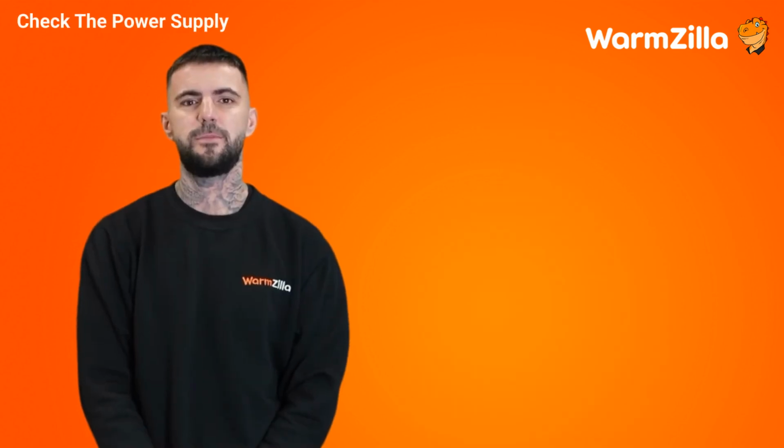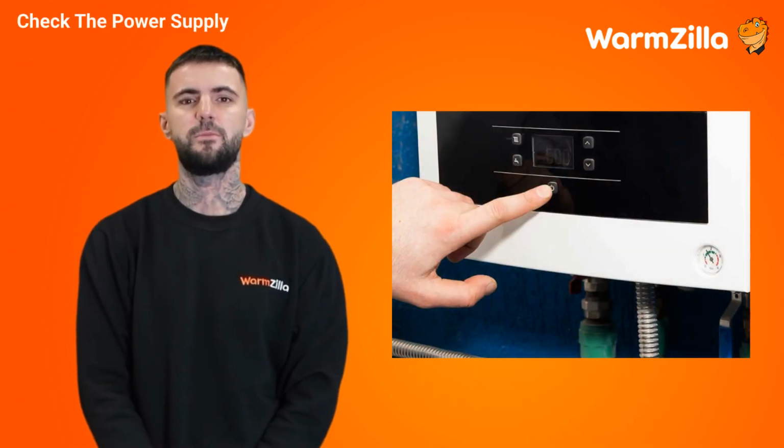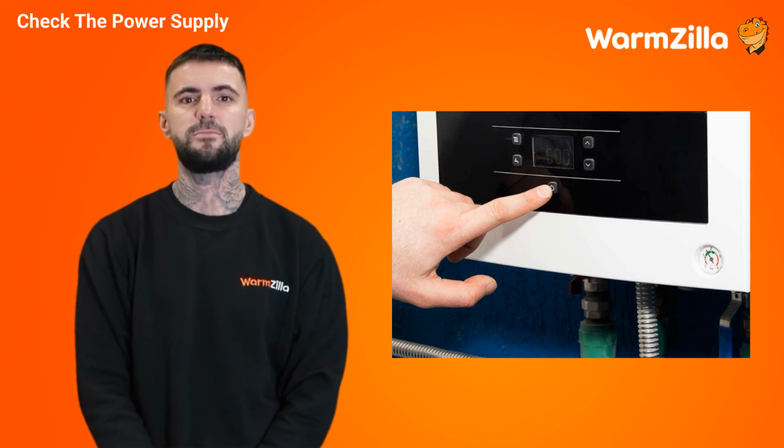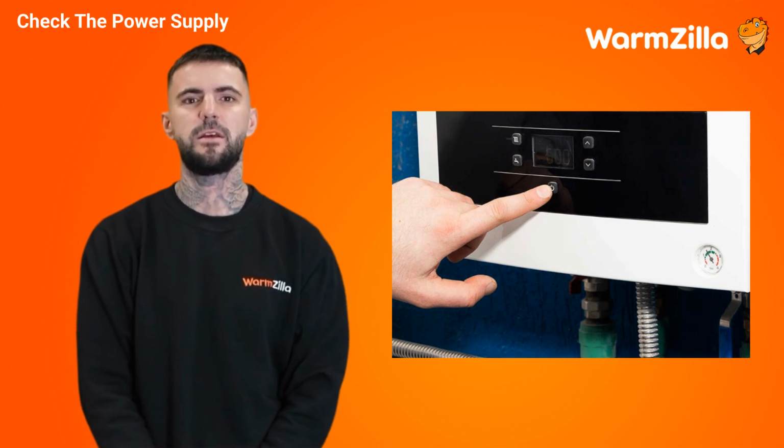Check the power supply. It could be an electrical issue if your boiler doesn't turn back on after the reset. Ensure the boiler is plugged into a working power socket and no circuit breakers have tripped. For those who turned off their boiler via the fuse spur switch, a fuse could have blown if flipping the switch had not restored power to the boiler. While most of these checks can be completed relatively quickly, if you're struggling to reset your boiler, we highly recommend calling an expert for help.